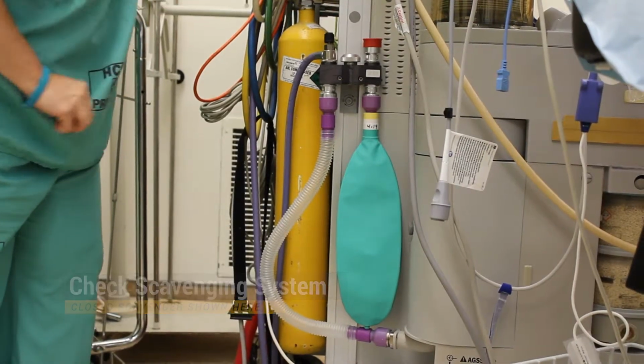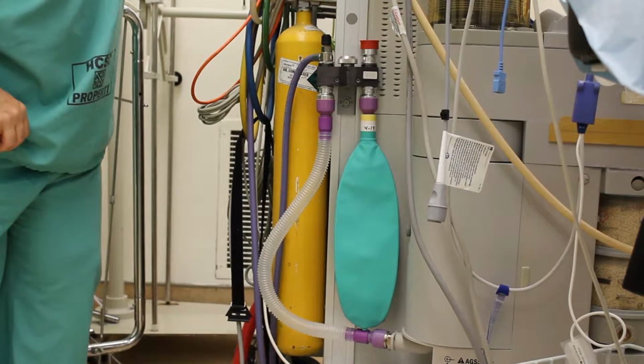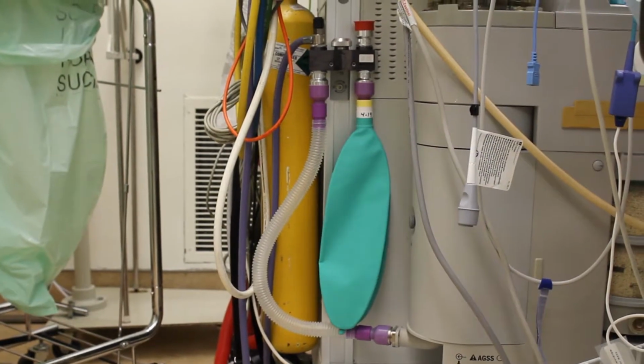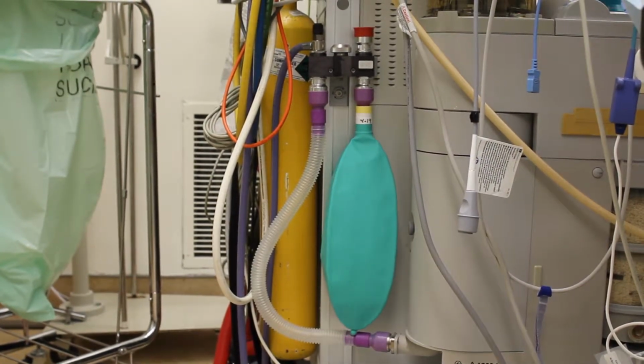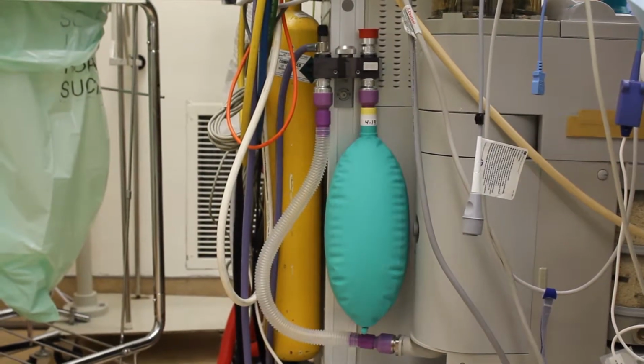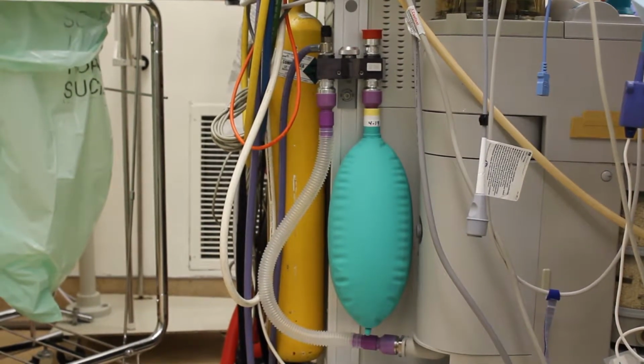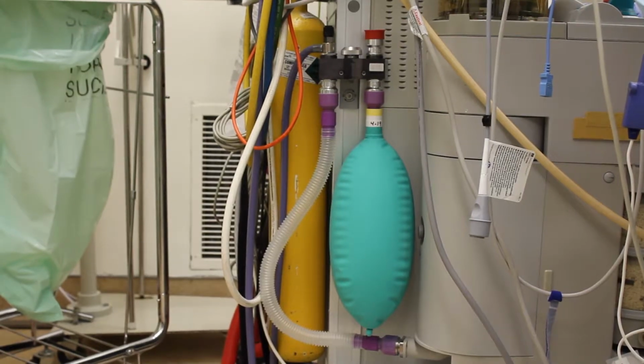To test the closed scavenging system, check that the reservoir bag does not fully distend when holding the oxygen flush button with the APL valve open and the Y-piece occluded. Also confirm that the reservoir bag does not remain fully collapsed, as this may indicate too much suction. In this example, the suction is set too low, as shown by the fully distended reservoir bag and the sound of waste gas escaping into the room.